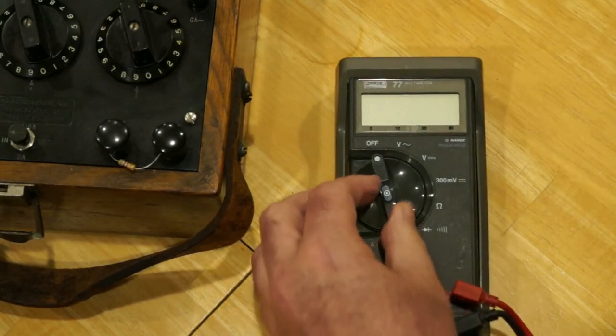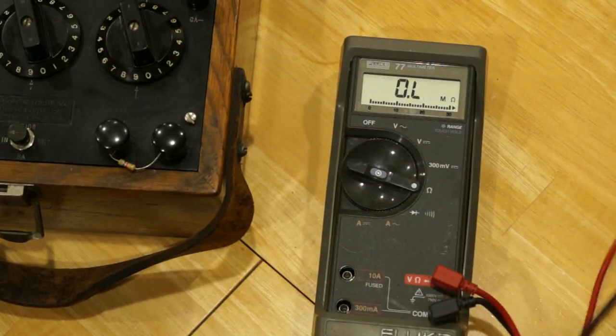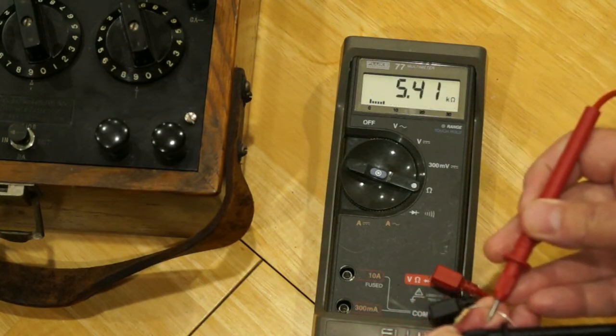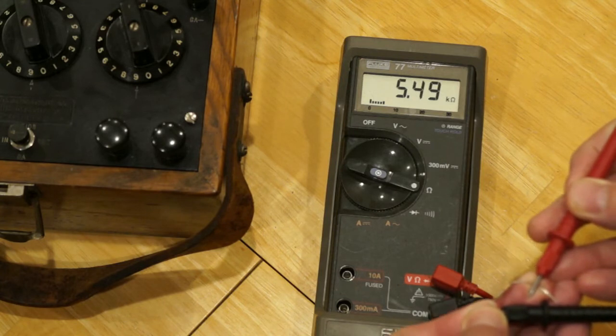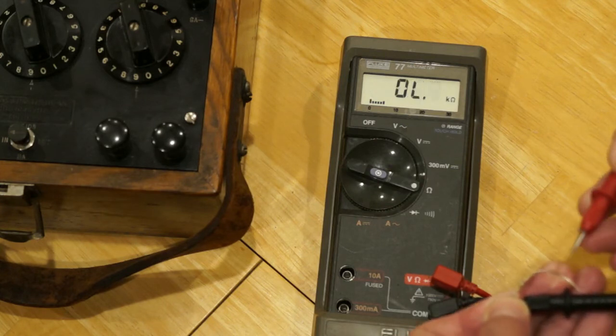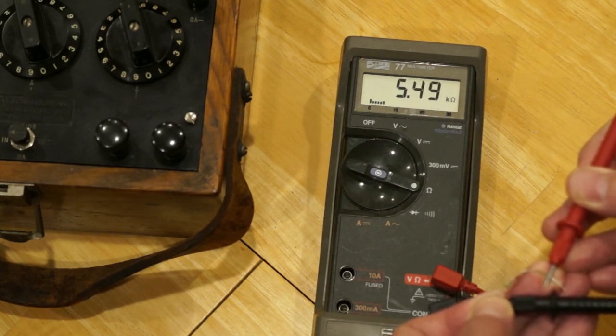We'll use this old Fluke meter, which is not the most accurate device, but it's probably good enough for our purposes here. I've got it set for resistance and we're going to take the resistor out of the terminals on the bridge. Connecting — just holding the leads here — we see we are at 5,499. We actually have an extra digit of precision off of the Leeds & Northrup Wheatstone bridge. So that agrees almost exactly — in fact, exactly — with the reading we got off of the Wheatstone bridge, which was 5,499. And we have 5.49 here.